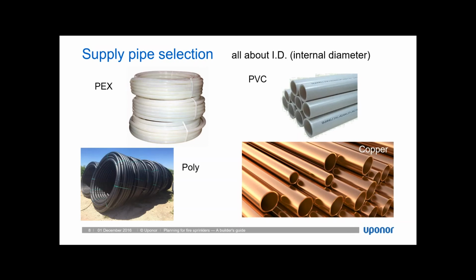3/4 inch as a supply line for a residential sprinkler system is often going to lose very significantly high amounts of pressure. You can have very small distances of 3/4 inch, and you may not lose more pressure than would be allowed for the sprinkler system demand. However, as soon as you exceed even 20, 30, 40 feet of 3/4 inch pipe at standard sprinkler system flows, you're going to see some very significant drops in your pressure. So if at all possible, 3/4 inch supply lines should be avoided when you're supplying a residential sprinkler system.